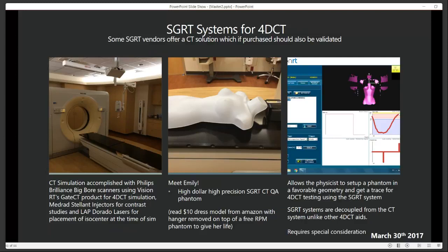SGRT systems on CT are another decoupled system. They're uniquely decoupled because they don't ride the couch like the Anzai belt, the Bellows system, or RPM. This is Emily. She's a very high dollar, high precision SGRT QA phantom. That reads as a $10 dress model from Amazon, riding on top of my RPM phantom that I got for free. If you put her on the couch, you have to tell the system, because it's not riding the couch now, how fast the couch is moving, which is based on your CT protocol.